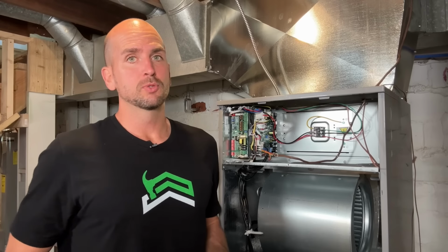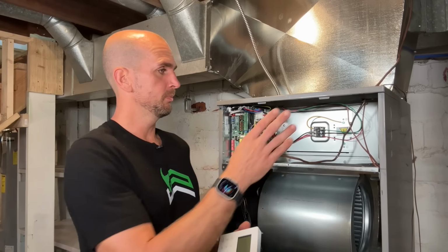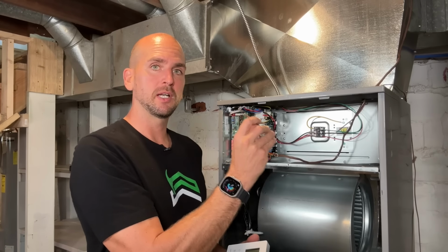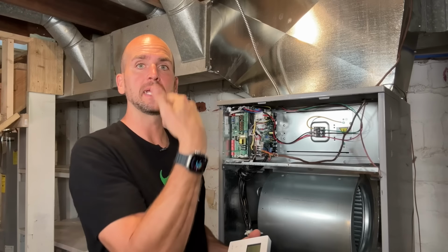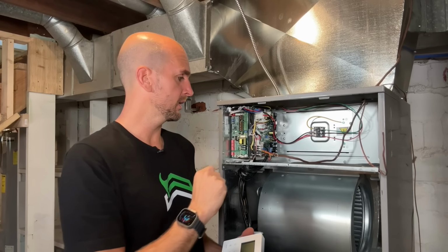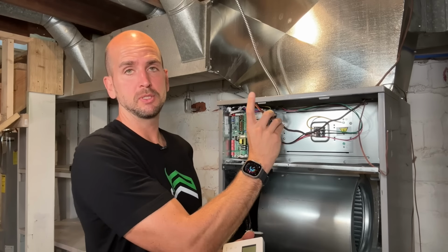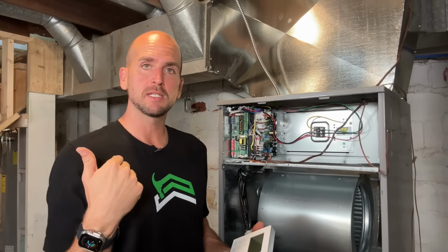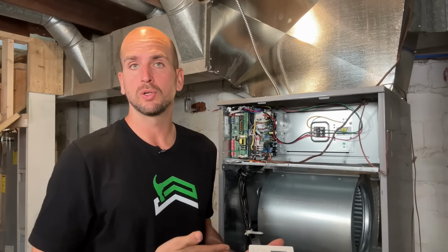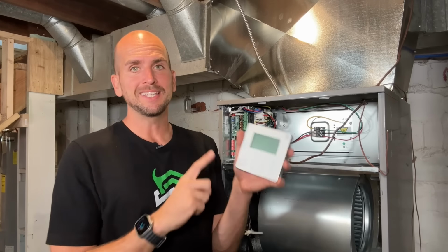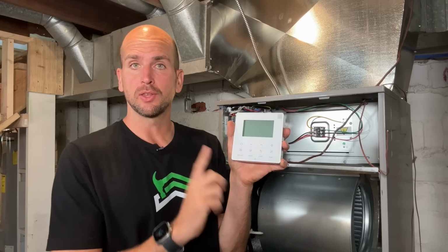So really on the home stretch here, and now we just need to make the connection, a 2-wire connection between the air handler and the outside condenser. So we'll make that connection. And then also a connection between the air handler and a thermostat. Now when it comes to thermostats, you have about 4 different options that Mr. Cool actually provides to you. The easiest is going to be actually to use their thermostat.